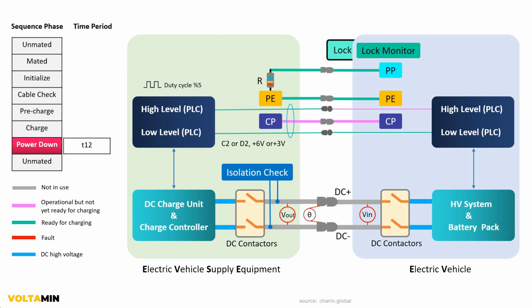At the power down phase, T12, the electric vehicle supply equipment, EVSE, disables its DC output after confirming that the EV no longer requires energy transfer. The EVSE opens its internal DC contactors, isolating the DC plus and DC minus lines, and fully de-energizes the system. The DC plus and DC minus lines turn to a non-energized state, signifying the absence of high voltage. Meanwhile, the communication lines, control pilot and proximity pilot, still remain active to ensure continuous system monitoring and confirm the safe disconnection process. This phase ensures that the EVSE and EV are safely powered down, concluding the charging session securely.